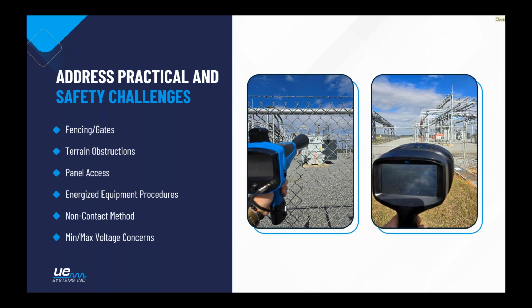In the two pictures I have here, one with a traditional unit and one with an acoustic imager, we're able to overcome the challenge of fencing, barriers, to actually inspect substations. So we don't have to change our PPE requirements because we're not going beyond the gate. We don't have to have permits. If we were a service provider here, we wouldn't have to have an escort employee to get into this part of the facility. And just like with infrared, we have that option of inspecting from a distance if we have the right pieces of equipment with us.